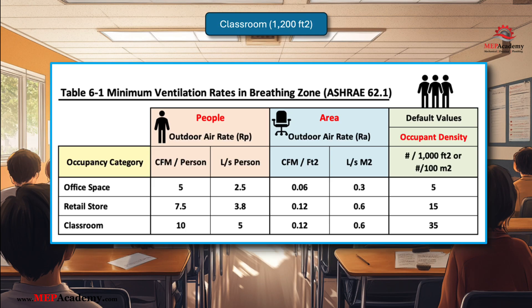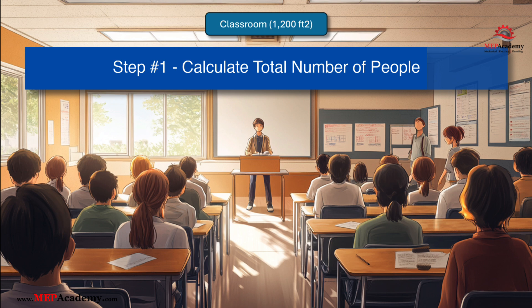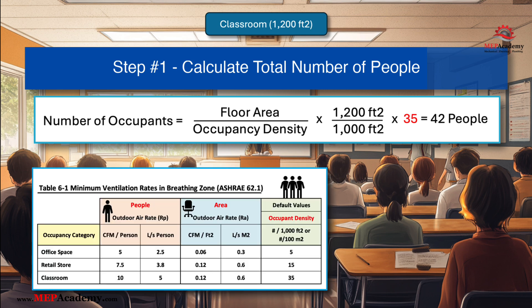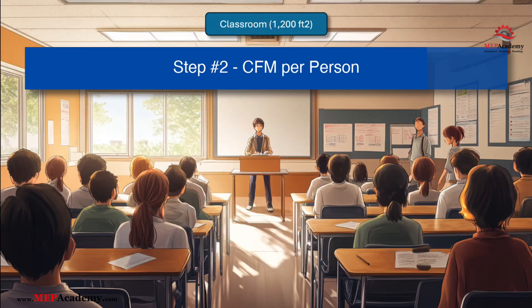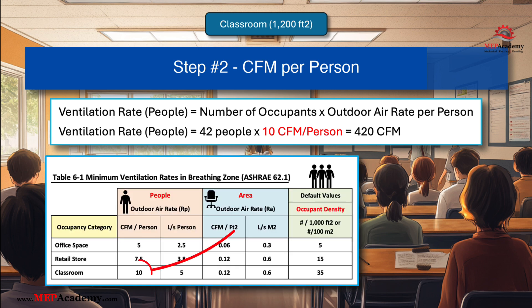Example 3: Classroom. Given data — Occupancy Type: Classroom; Floor Area: 1,200 sq ft; Occupancy Density: 35 people per 1,000 sq ft; Outdoor air rate per person: 10 CFM per person; Outdoor air rate per area: 0.12 CFM per sq ft. Step 1: Number of occupants = (1,200 sq ft / 1,000 sq ft) × 35 people per 1,000 sq ft = 42 people. Step 2: Ventilation rate (people) = 42 people × 10 CFM per person = 420 CFM.